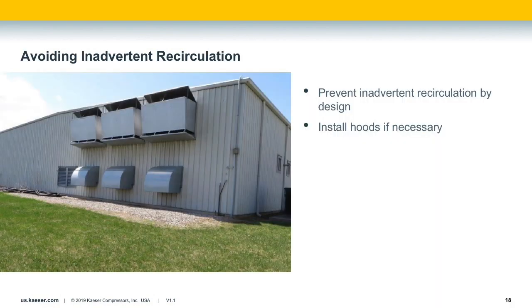The best ways to avoid this are to use ducting, employ thermostatically controlled inlet and recirculation louvers, and to have a prevailing direction of cooling airflow whenever possible. Bring cool air in on one side of the room and exhaust warm air out on the other. Having the majority of the airflow in one direction helps prevent accidental recirculation. Try to route exhaust air through the roof when possible, and take prevailing winds and other site conditions into account.